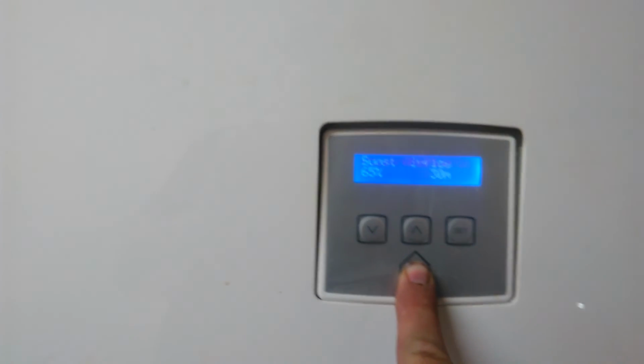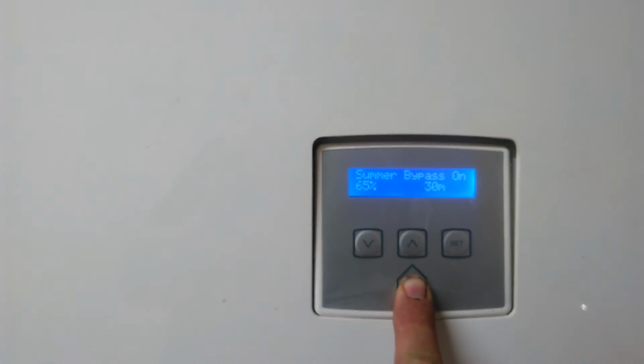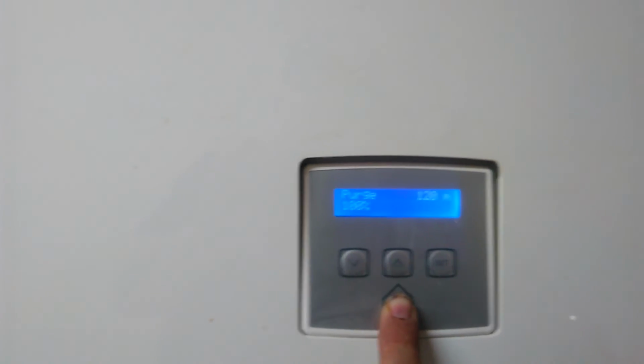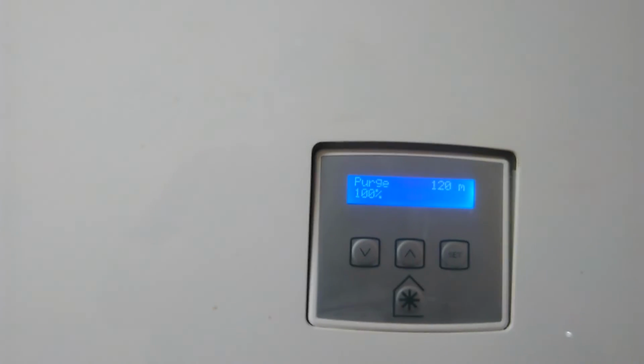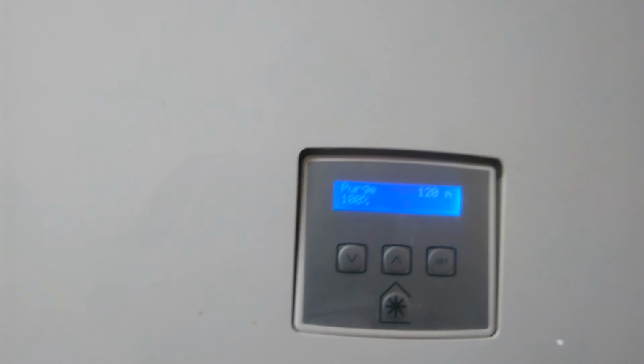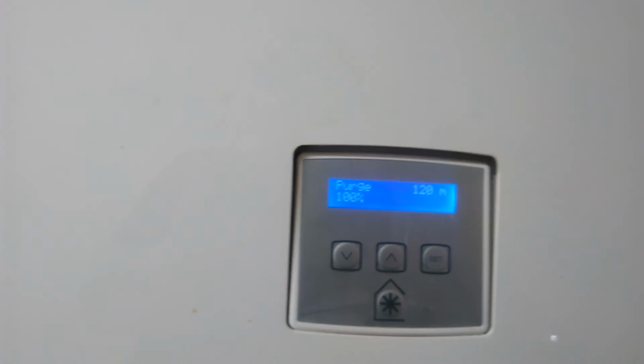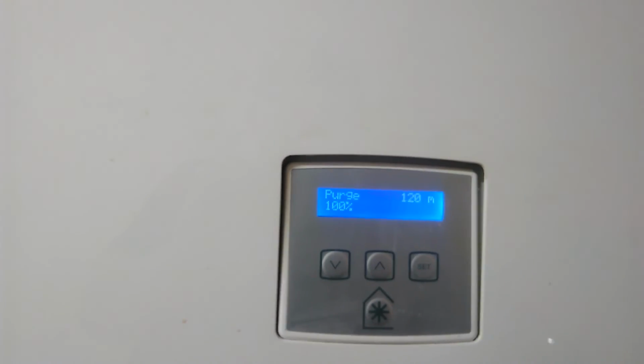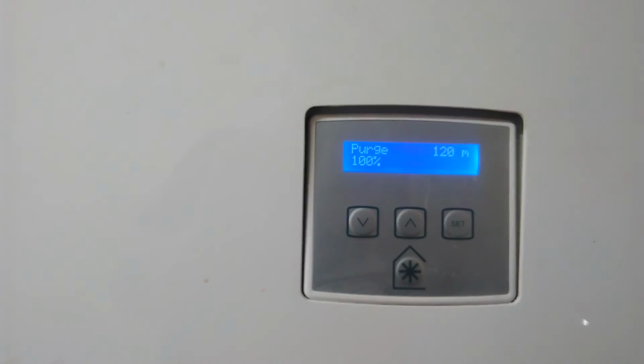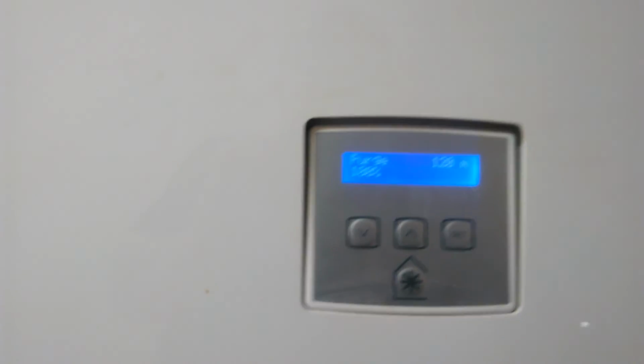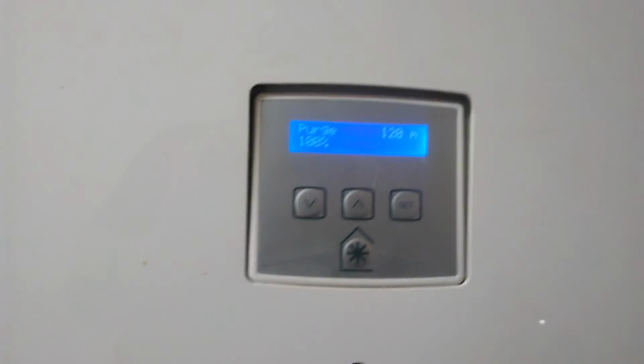Now, to initiate the purge screen, which offers cooling during the evening or early morning on what you know is going to be a hot day, keep your finger on the snowflake and purge comes up. Okay, so this offers cooling. It just basically acts as a large fan in the house. The heat recovery cell is switched off and air is dumped and brought in at 100% fan speed. So this can offer cooling during the evening and early hours of the morning, recommended on a hot, steamy day, as I said. Okay, so the purge will run for 2 hours.